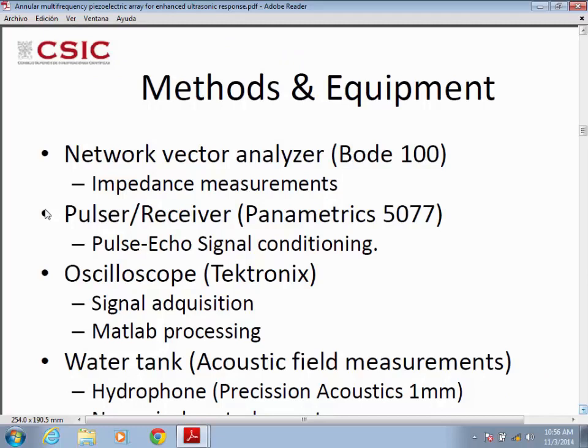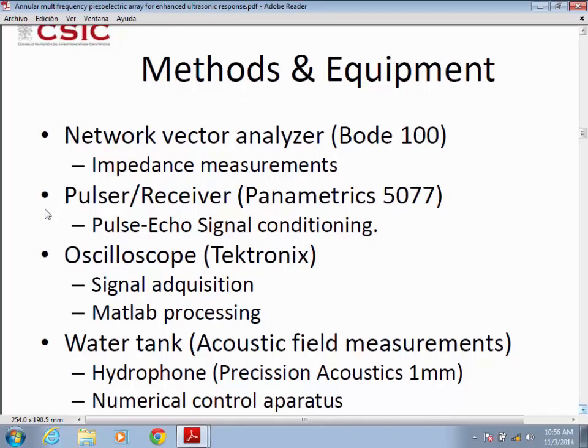We use these devices in order to make our measurements. We have a network vector analyzer to take impedance measurements of the transducer. Also, we have a pulser, a Panametrics pulser, and we are using pulse-echo signal conditioning with a negative pulse. Then we measure the signal back with an oscilloscope, and MATLAB is used to process this. For the field measurements we used a water tank with the transducer immersed, and with a needle hydrophone, we made some precision acoustic measurements of the near field. This is also controlled by a CNC machine, so we have precision in space and in the measurements.